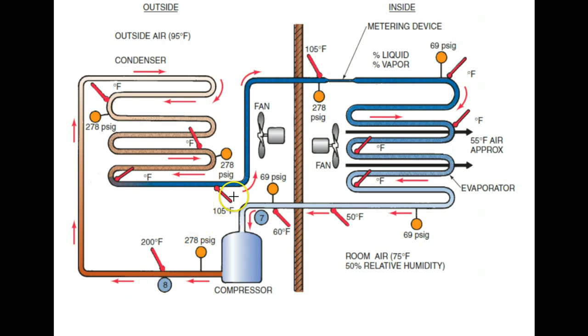Now, just like the superheat method of charging, when you add the first few increments of refrigerant, you're not going to see a huge amount of change in the subcooling levels or temperatures and pressures. It seems to be at the beginning of when you're charging a system that you'll add this refrigerant and the changes are small, very small, that you can't even see.